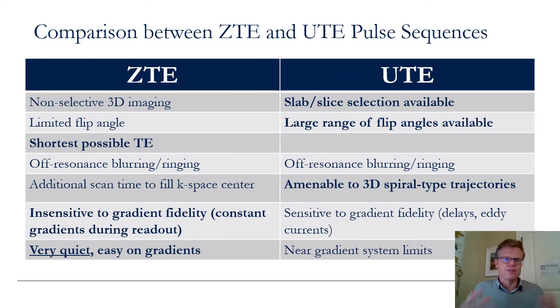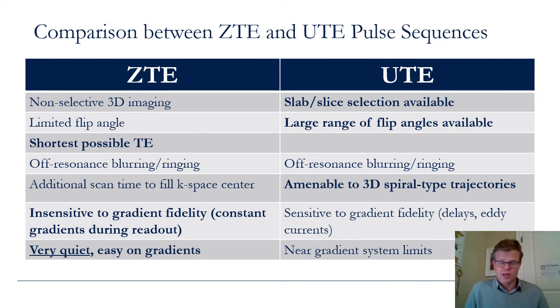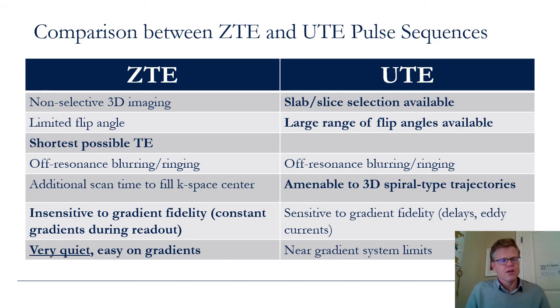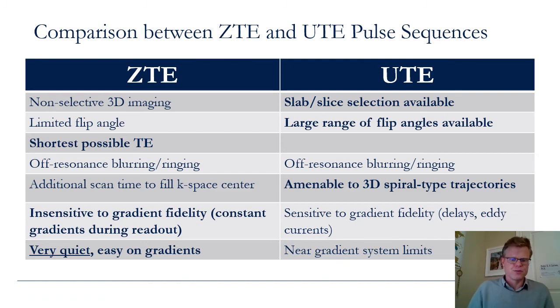Finally, comparing ZTE and UTE — ultra-short TE — pulse sequences, which often come up together: UTE has advantages in that it can do slab or slice selection and is more open-ended in the range of flip angles available. ZTE's advantages are that it provides the shortest possible TE — giving the best short T2* signal — it is very insensitive to gradient fidelity so you don't need to worry about eddy currents or gradient delays, and of course it is silent, which is not true for most UTE sequences.